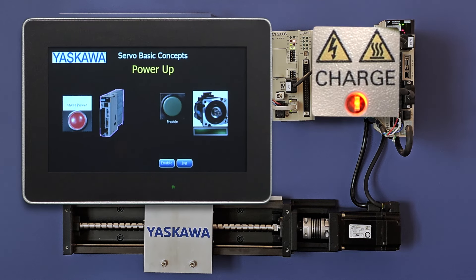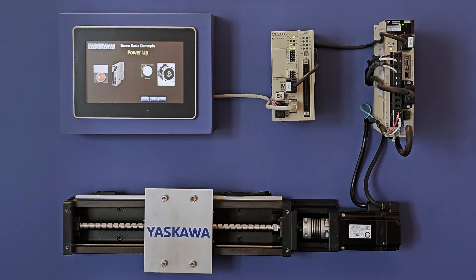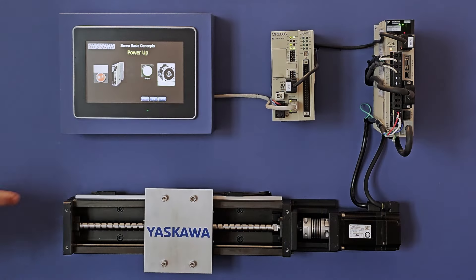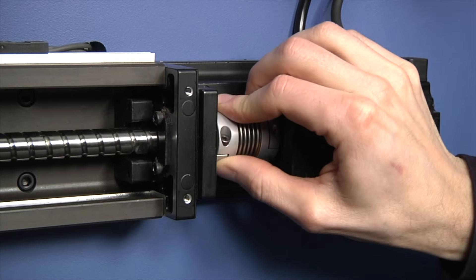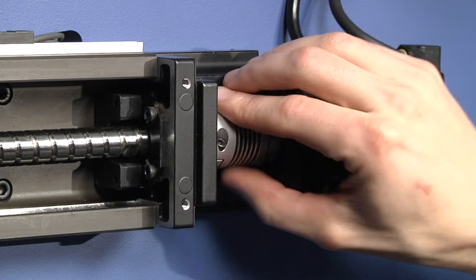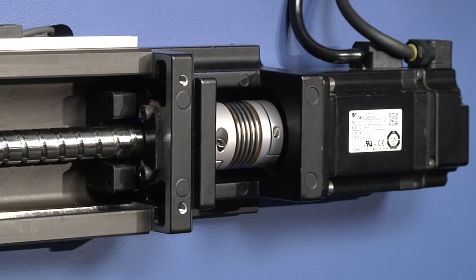We refer to this as main power. The main power input allows flexibility in wiring to the servo amplifier. The third stage is to energize the servo motor — we refer to this as servo enable. This signal to enable the motor comes from the controller. Servo enable doesn't mean the motor is moving; it only means that it's ready to move when commanded. Before the servo is enabled, the shaft will easily move, but if you manually try to turn the shaft while the servo is enabled, it will hold its position. You may hear a hissing sound as the servo works to maintain this position.